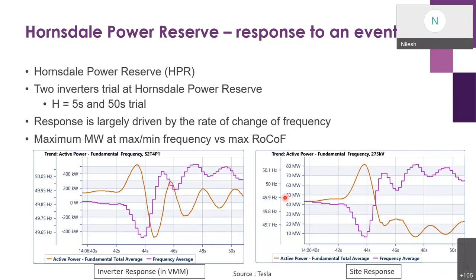It was a frequency event, and the figure on the left side is the response from the inverter, and the figure on the right side is the response from the site. Now, when we look at the site response, most except two inverters, other inverters were in a grid following mode, while the two inverters were in grid forming mode. And you can see the purple is the frequency, and the other color is the response from the inverter.